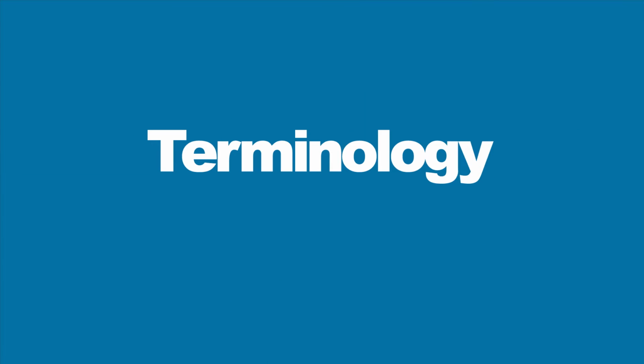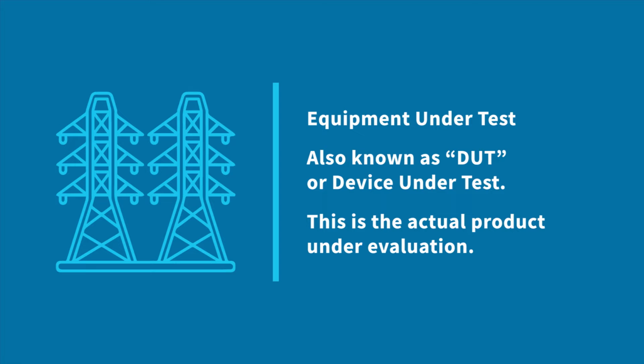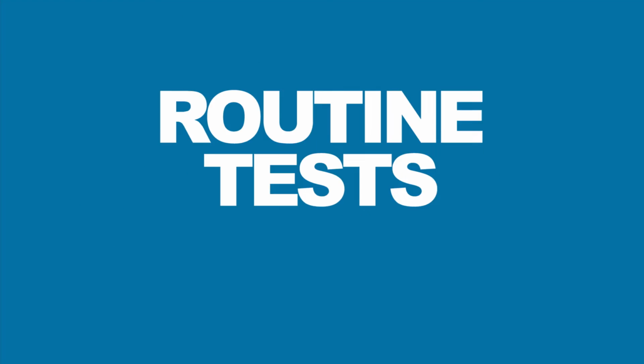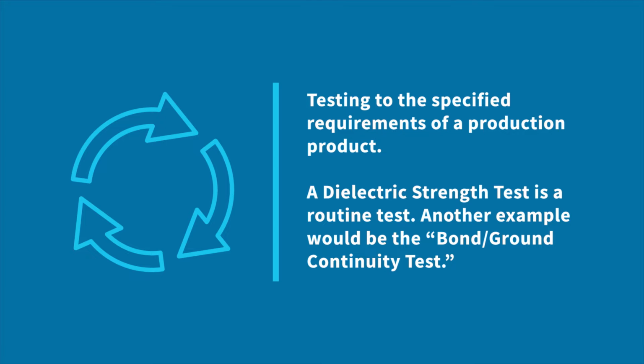Terminology. EUT: equipment under test, also known as DUT or device under test. This is the actual product under evaluation. Routine tests: testing to specified requirements of a production product. A dielectric strength test is a routine test. Another example would be a bond or ground continuity test.